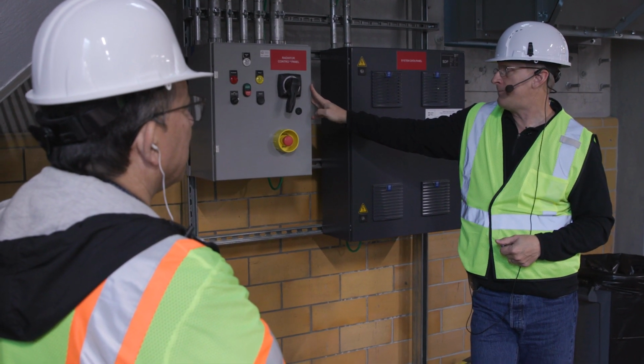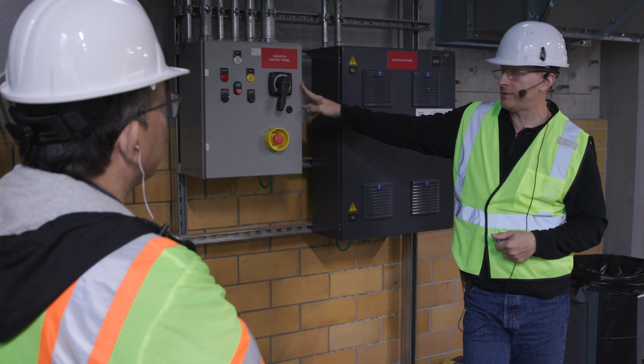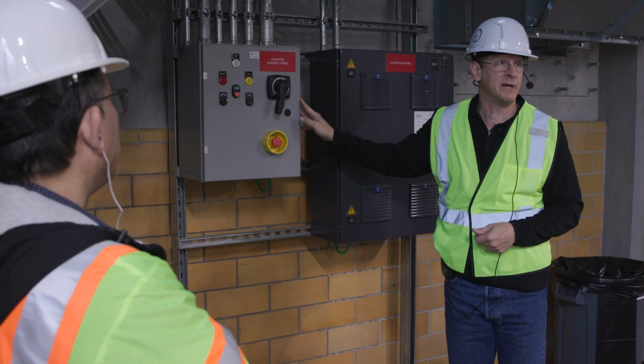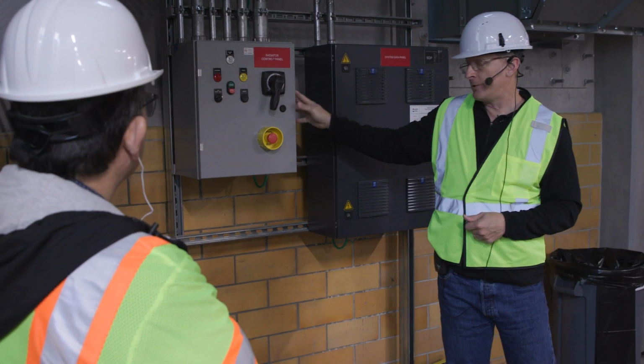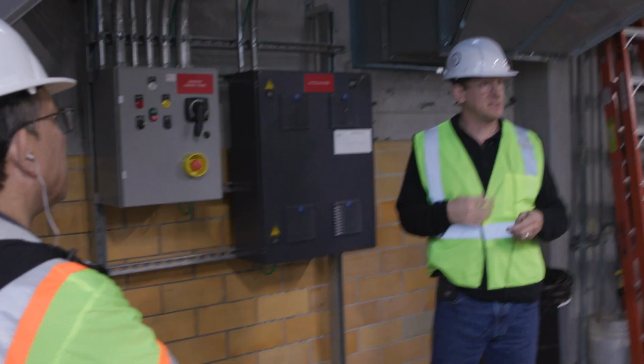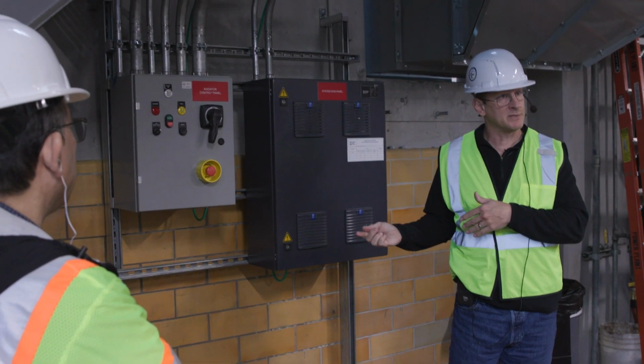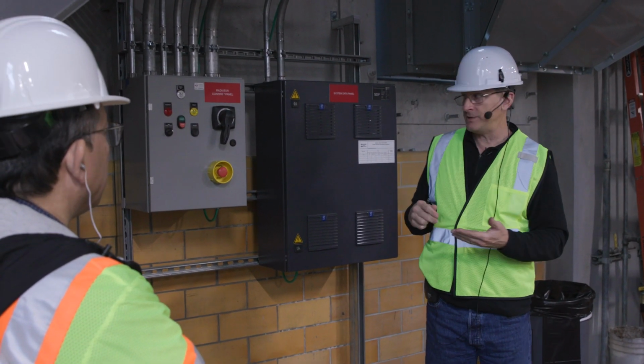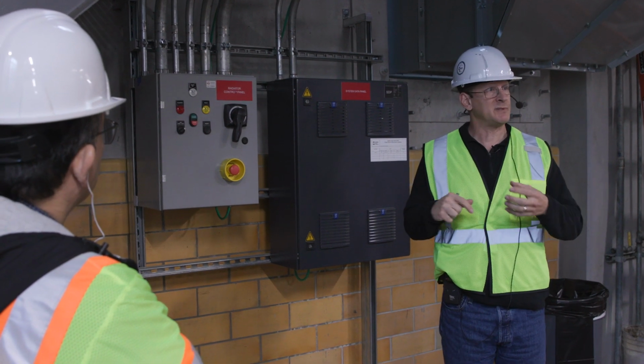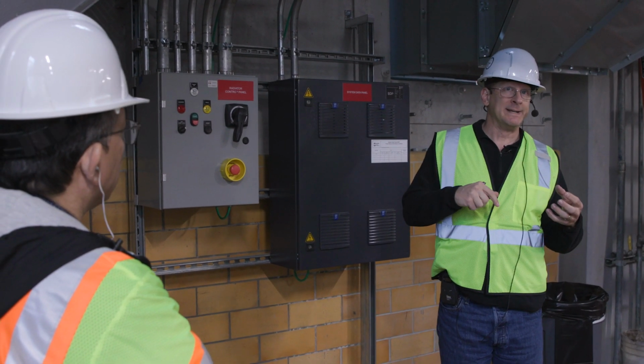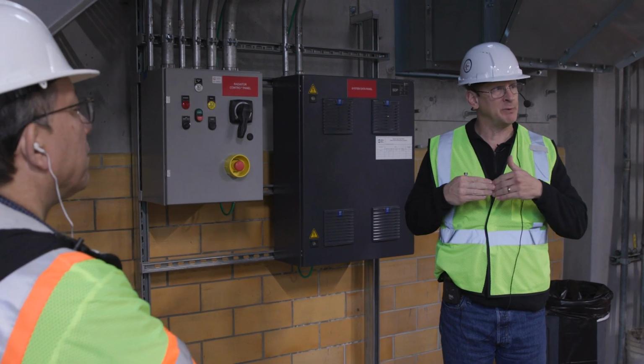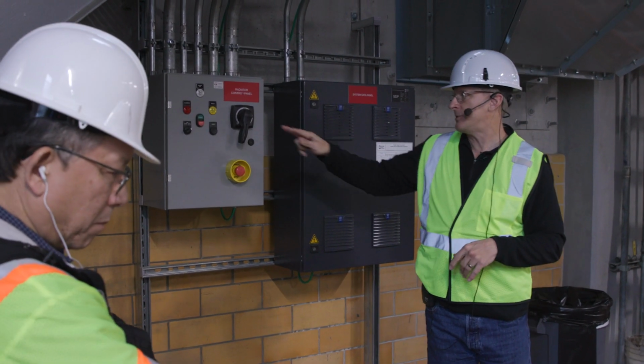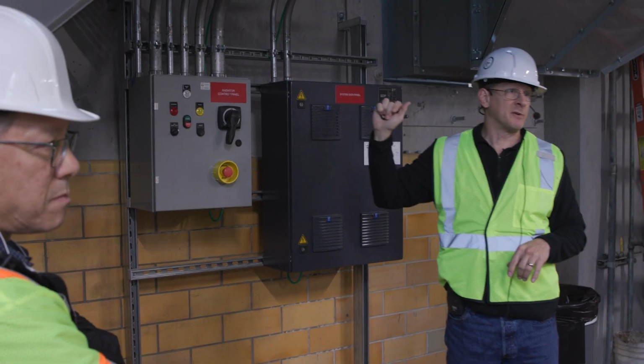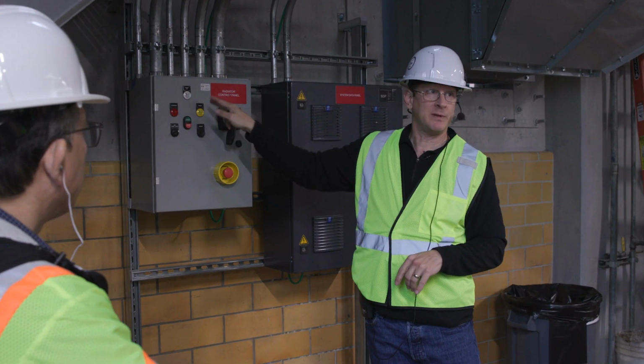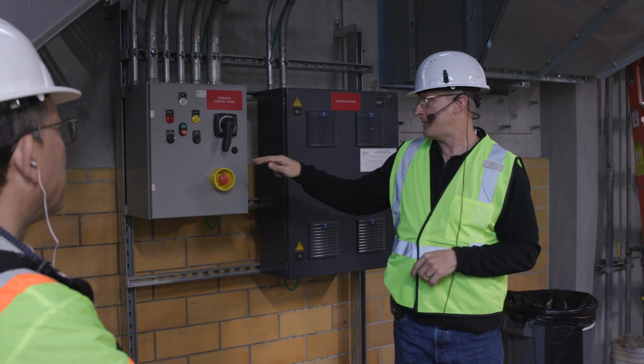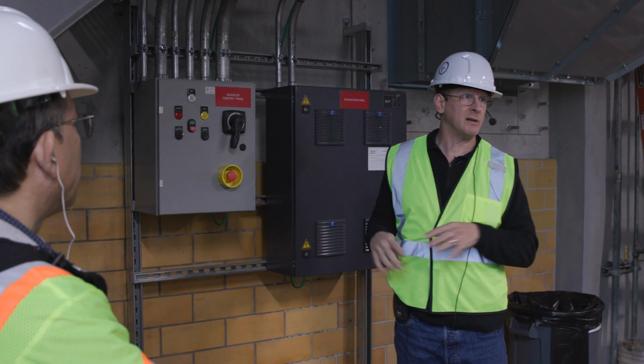One thing that we found out about this particular panel in soft start is whenever we energize the panel during a first start of the unit, it does an initialization of some sort with the soft start, and it actually runs through an alarm sequence. When it receives voltage, it starts to initialize with the voltage too low, but then ultimately comes to 480, and it will actually trigger a fault. So on a first start, you might see a fault condition pop up here and at the UCP. We have to clear that with the reset and at the UCP, and then it'll be fine.